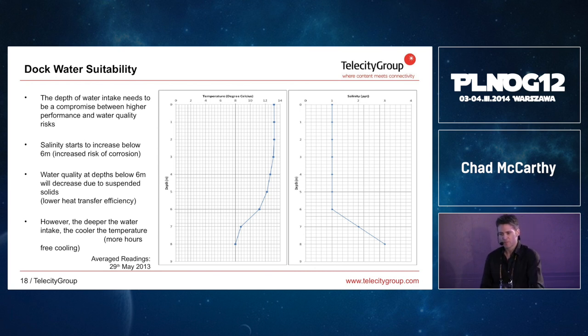And there is also something which we call suspended particles. The water near the bottom of the dock is full of suspended particles. It's not clear, which means that we will have maintenance problems. If we take that water into our system, then we have increased filtering. We have the buildup of scale. So that's why we selected for our system the depth of exactly 6 meters, which is before the salinity starts to increase. The water does still have some salt content. It's a mixture of seawater and river water. But it's at a level where we can prevent scale buildup via the velocity of the water. So we keep the water moving fast enough through our system, then we don't get a buildup of scale.